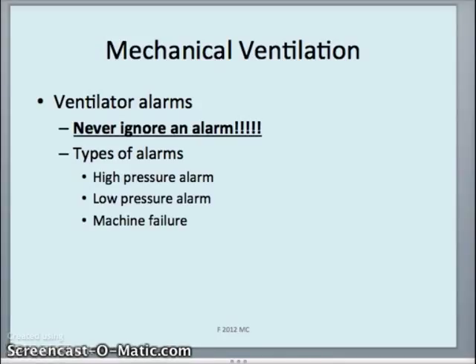People begin to ignore alarms, but there's been lawsuits where the patient's family have won considerable amounts of money because of the alarm fatigue that was experienced. So the first thing is never ignore the alarm. This also means that if you have a patient with a ventilator, you need to be within earshot of that patient so that you will be able to hear the alarm when it goes off.